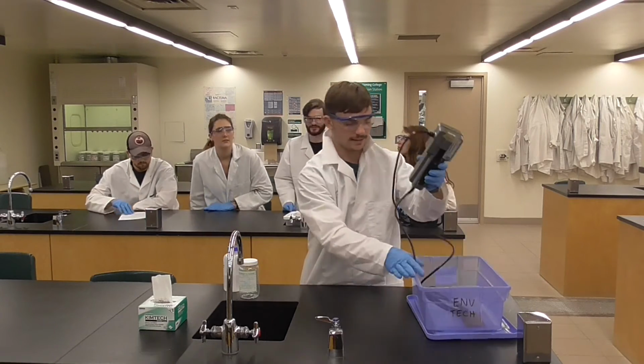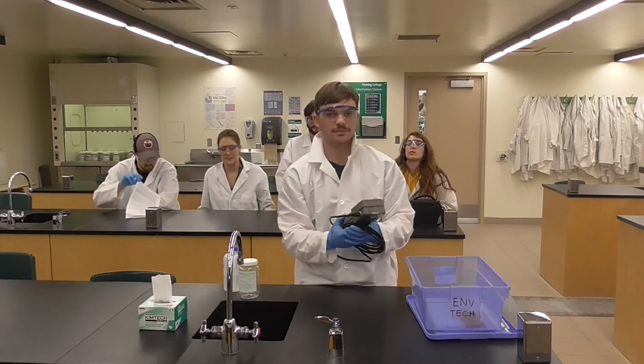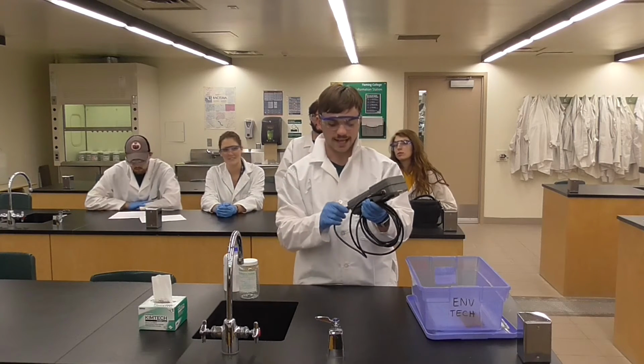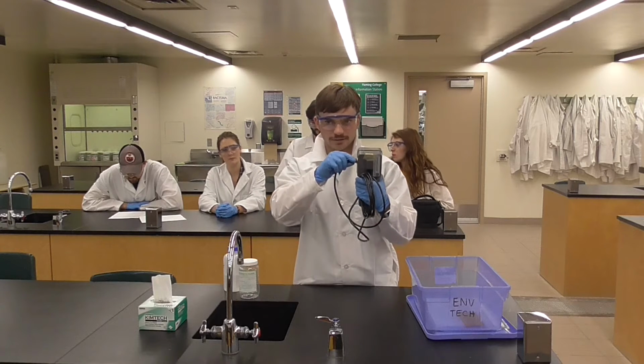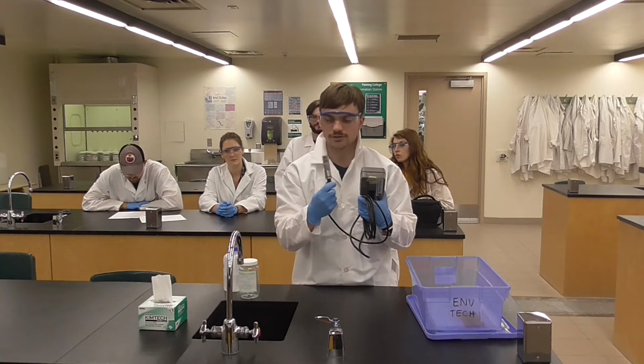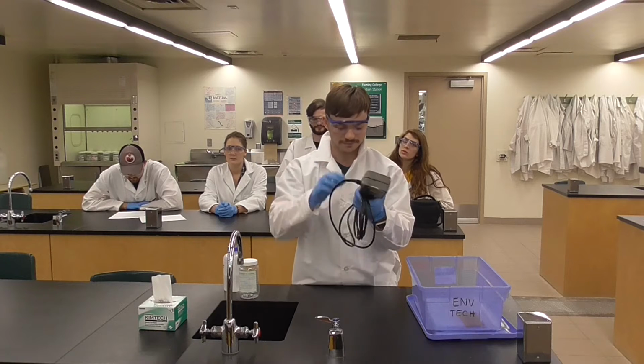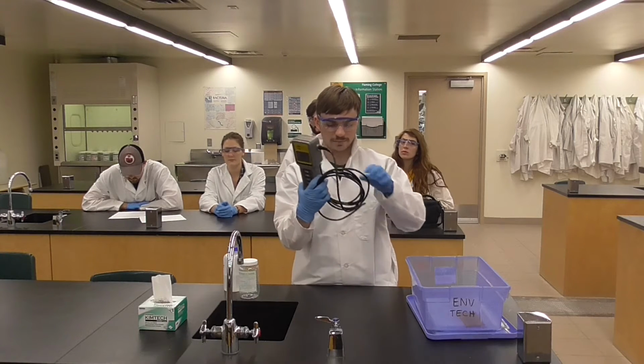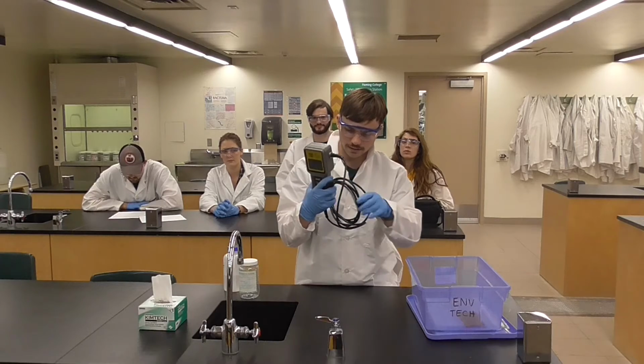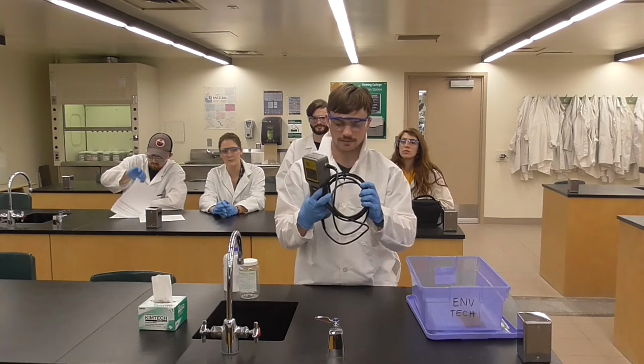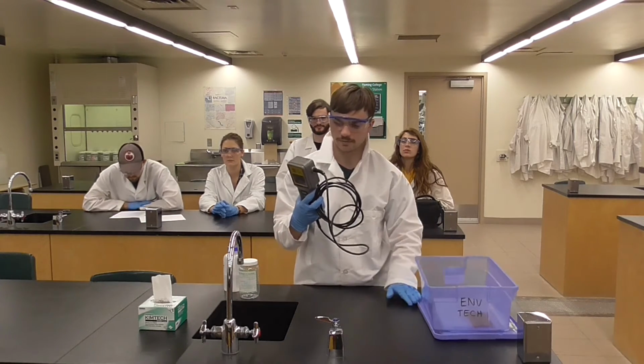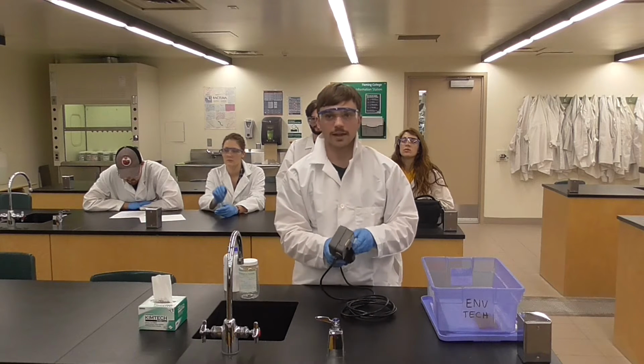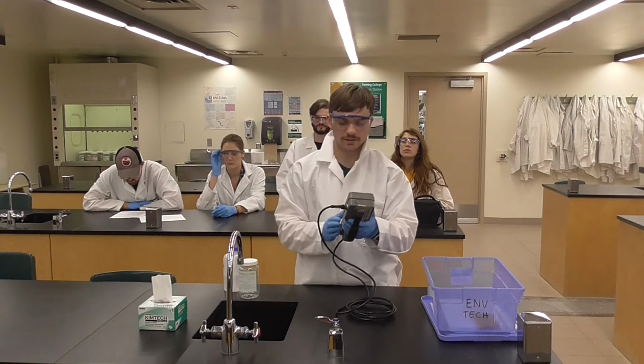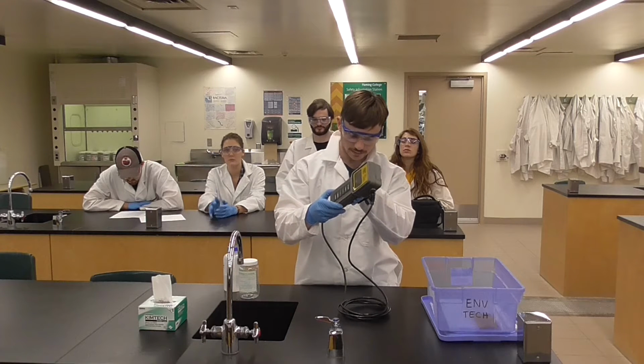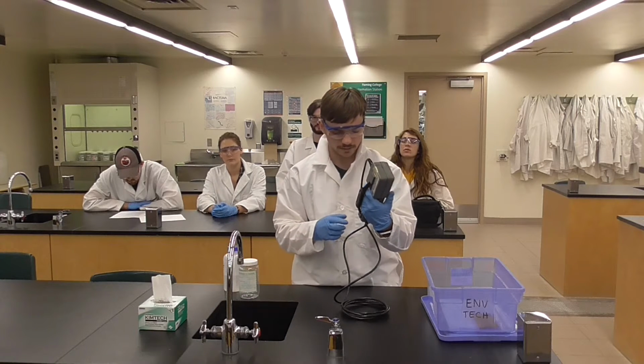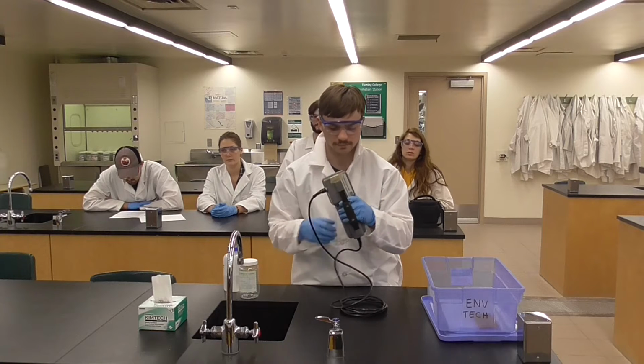First step in using a conductivity meter is ensuring that the cable and the electrode are both properly installed on the meter. I'm going to inspect, make sure there's no loose wires or any damage to either the cable or the electrode. And then I'm going to check the whole meter to make sure there's no visible damage anywhere that may cause problems while taking measurements.